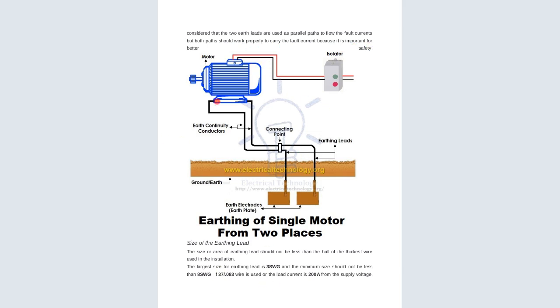So now look at this diagram. This is the earthing of a simple motor from 2 places. We are earthing it from 2 places, meaning from the supply side and from the ground side. This is our motor, this is our isolator, and this is the earth continuity conductor. You can see it is being earthed from that side and that side. That is the connecting point. The two of them are being connected, and they are meeting at the earthing leads. The earthing leads are here, and they are meeting at the earth plate. The earth plate is normally buried in the ground. That is the ground, that is the earth mass.